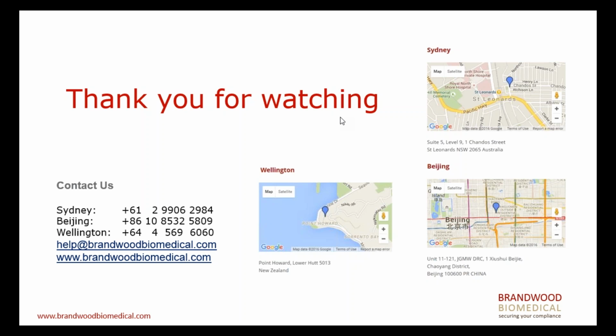So you have to make sure that your literature search, if you're using that pathway, is well documented, you have looked at the level of evidence, and you have documented where you have your inclusion-exclusion criteria, for example. And in terms of substantial equivalence, I know that could be a challenge if you want to do that in China versus Australia. As I mentioned before, in China they want something that's approved already, a predicate approved in China, and they want to specifically compare it to that. Whereas in terms of substantial equivalence, you need to compare the obvious things like what are the indications and materials and biological characteristics, the key technical characteristics, what are the intended populations, and if there are any differences, then I need to provide a rationale for why that's not significant in clinical practice.